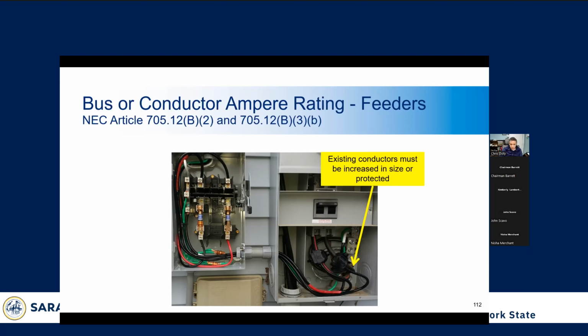You'd have PV voltage tapped into the utility line coming in, and those taps connected to a disconnect. That's potentially possible. That would be if these were connected in above here, I believe, because this is the conductor going into the building, so that's going into the apartment, and the main breaker is right here. So you're adding in additional current, which you would not otherwise have, and this breaker is not protecting against. This is not super common, but there are places that you might see it, and you have to be cognizant of that.